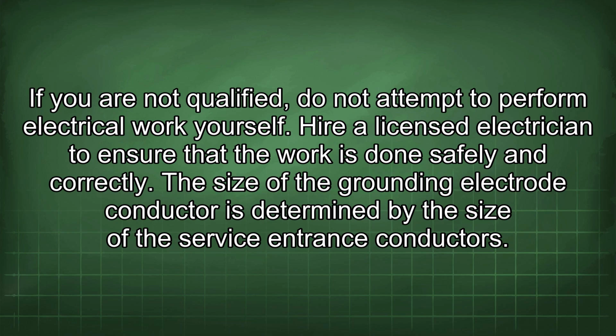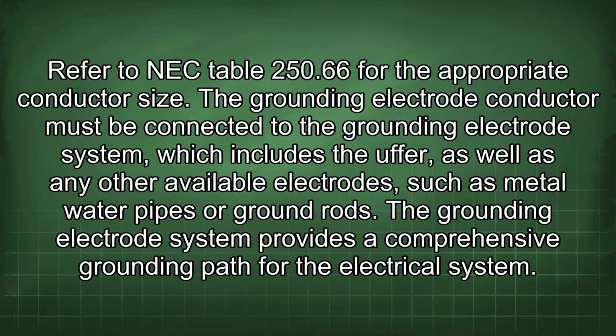The size of the grounding electrode conductor is determined by the size of the service entrance conductors. Refer to NEC Table 250.66 for the appropriate conductor size. The grounding electrode conductor must be connected to the grounding electrode system, which includes the Ufer, as well as any other available electrodes, such as metal water pipes or ground rods. The grounding electrode system provides a comprehensive grounding path for the electrical system.